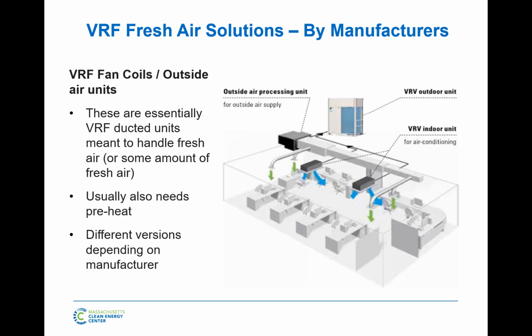So what that means is a DX, DX is short for direct expansion, which means refrigeration. So a refrigerant system, which is what VRF and air source heat pumps are, isn't really designed to take air straight from 0 degrees to 70 degrees. Again, extracting the heat outside with a condenser is no problem. We talked about that, right down to 0, -4, -10, -20. But raising the temperature of air from 0 to 70 is an issue. So they have a minimum entering air temperature in the 20s. So you need some preheat there.